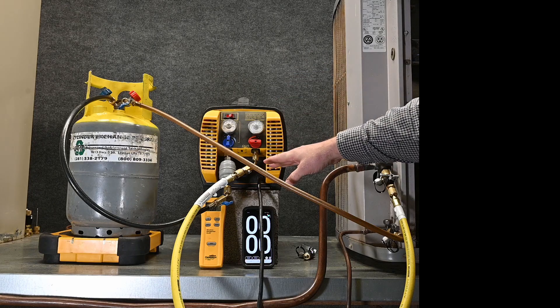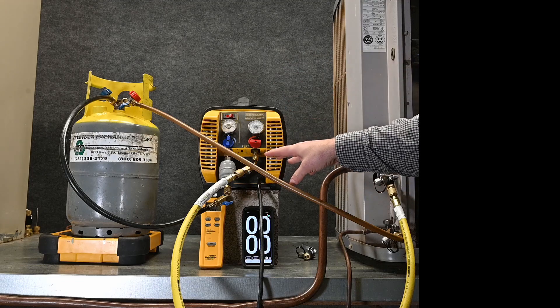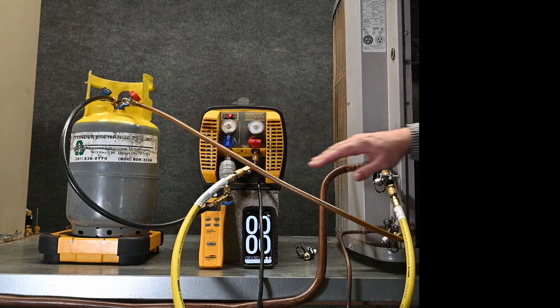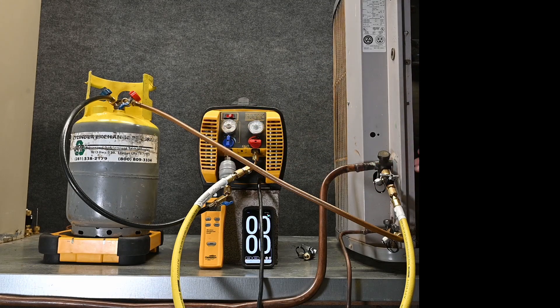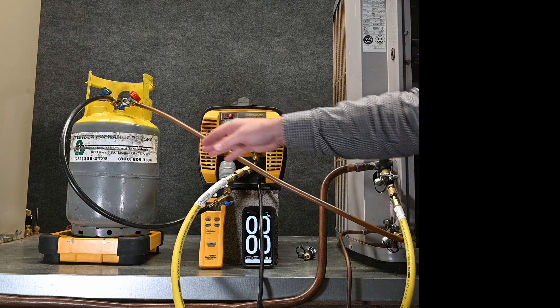But instead of hooking my recovery machine up pumping liquid into the tank, we're going to hook a recovery machine up pulling vapor out of the tank and putting vapor back into the system. And the idea is that we're pushing that liquid back into the tank.